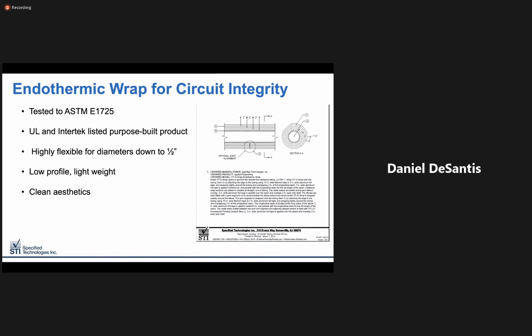The image on the right is pulled from our Intertek listing for a 2-hour rated enclosure around EMT. We'll be breaking that down a little bit further in just a few minutes, but this serves as the basis of the design for a lot of our electrical circuitry solutions.